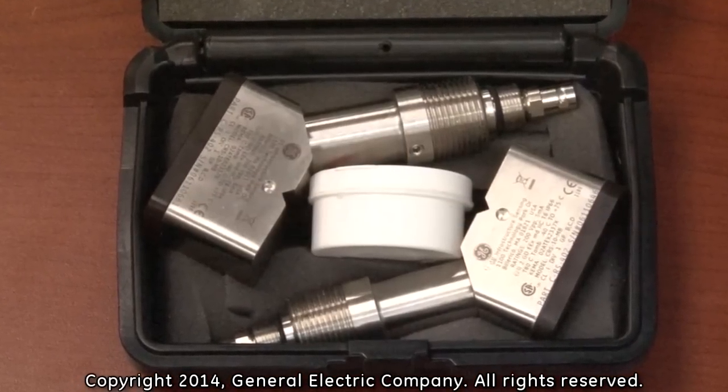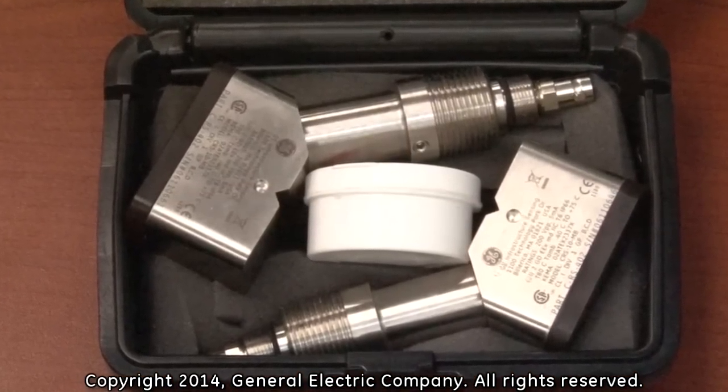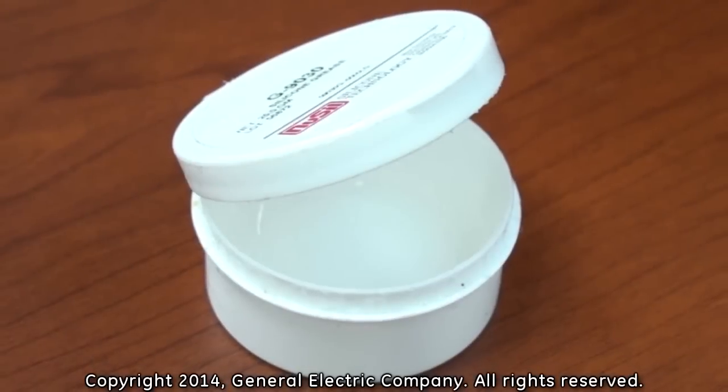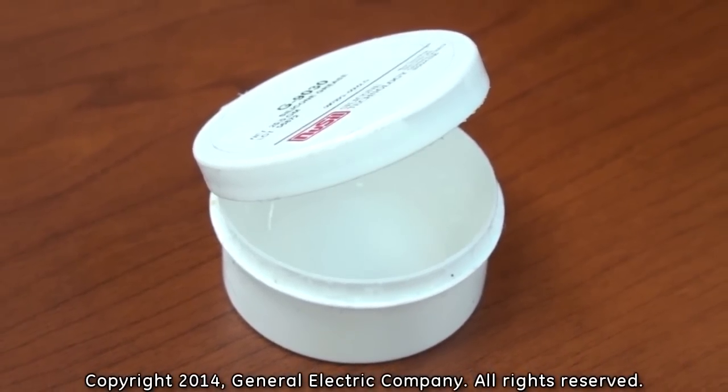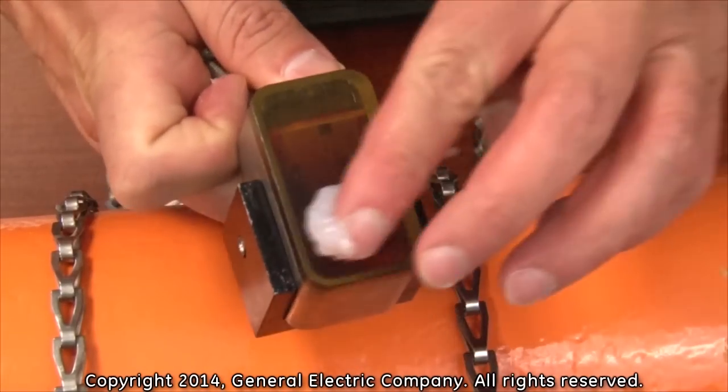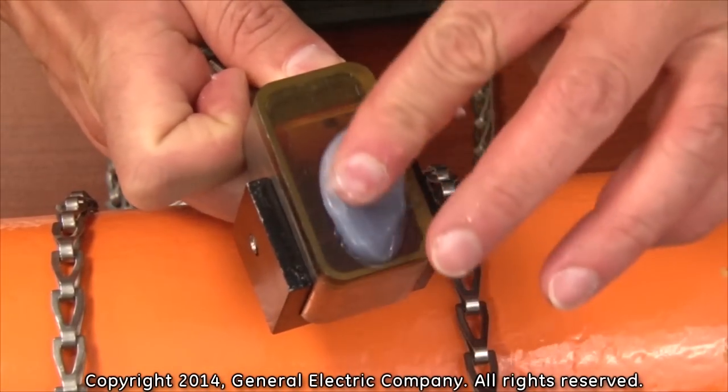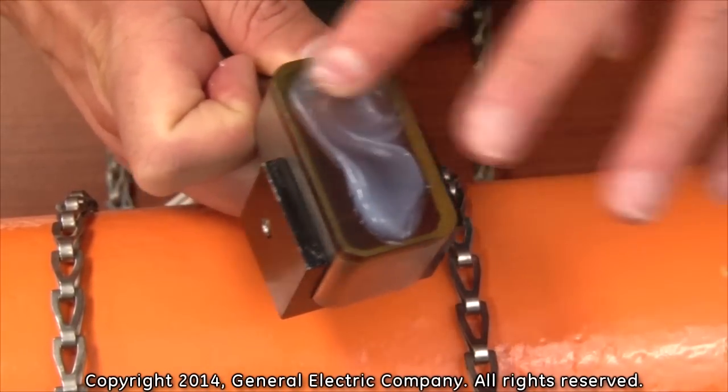Before installing the transducers, you must apply couplant onto the face of each transducer. Use only the recommended couplant for your specific transducers and application. Use as much couplant as you would toothpaste on a toothbrush and evenly cover the face of the transducer.